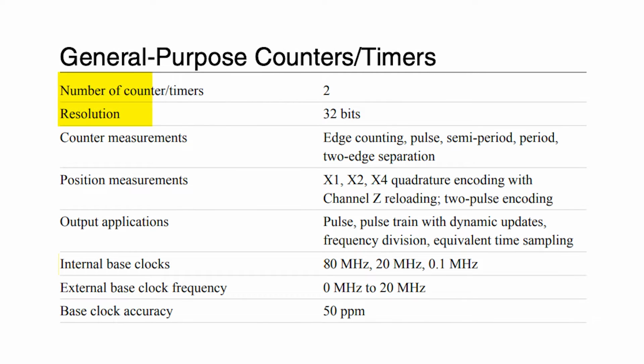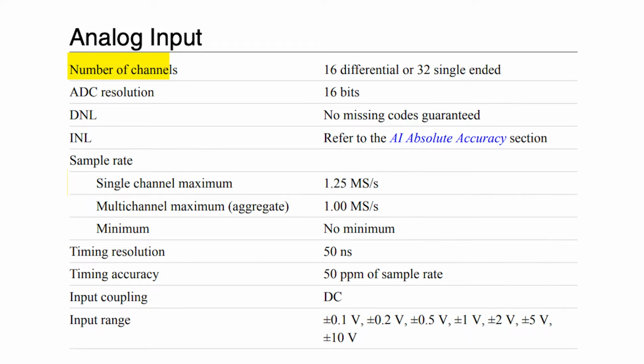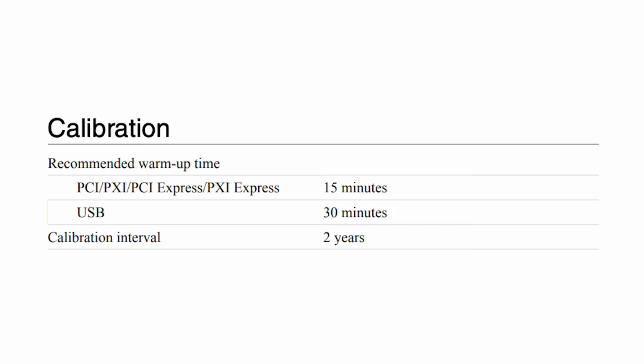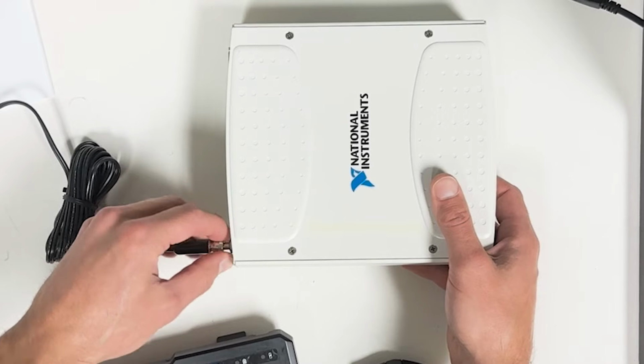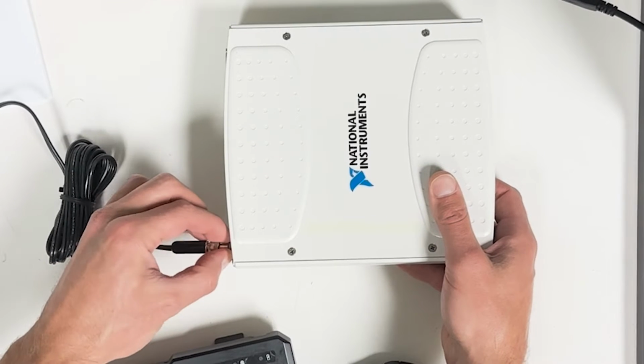This device includes two 32-bit counters, also referred to as timers, which operate at a rate of 80 MHz. Additionally, it features 32 single-ended or 16 differential analog input channels, each with a maximum sample rate of 1.25 megasamples per second, and 4 analog output channels. For optimal performance, the device should warm up for 30 minutes before use and be calibrated at least once every 2 years. To begin the calibration process, follow these steps.